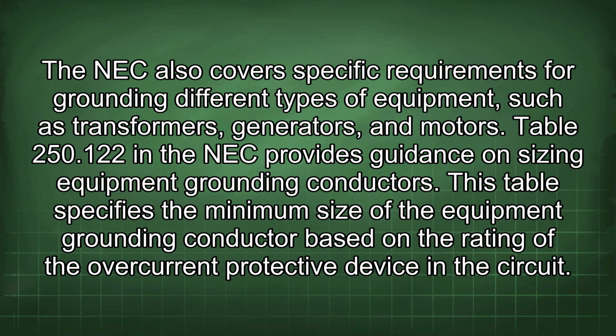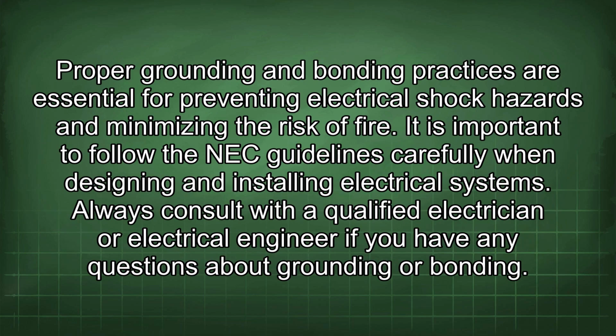Table 250.122 in the NEC provides guidance on sizing equipment grounding conductors. This table specifies the minimum size of the equipment grounding conductor based on the rating of the overcurrent protective device in the circuit. Proper grounding and bonding practices are essential for preventing electrical shock hazards and minimizing the risk of fire.